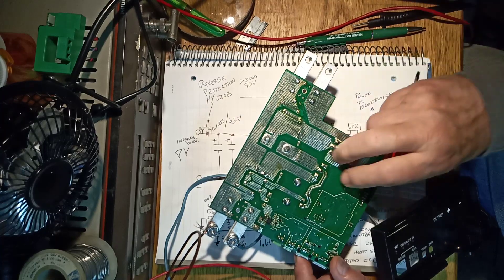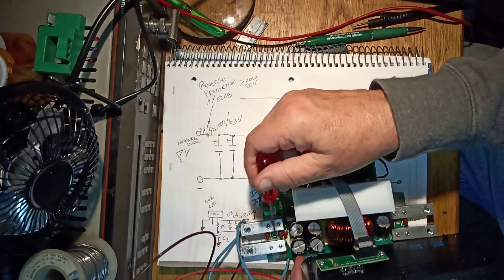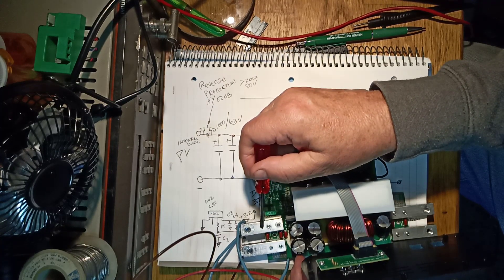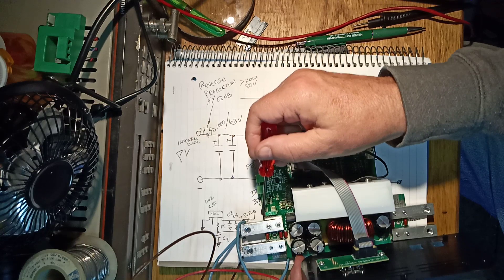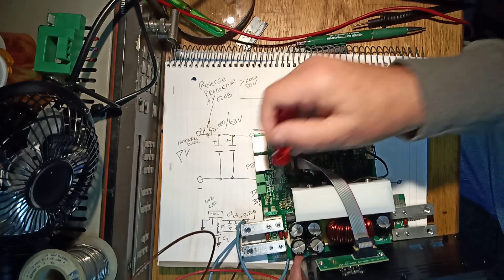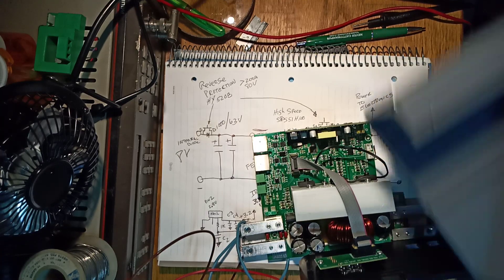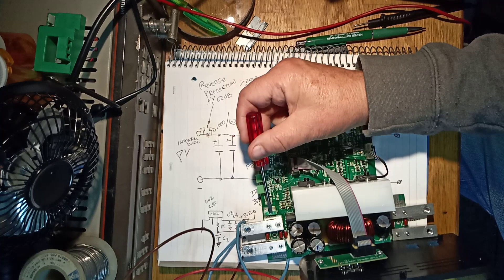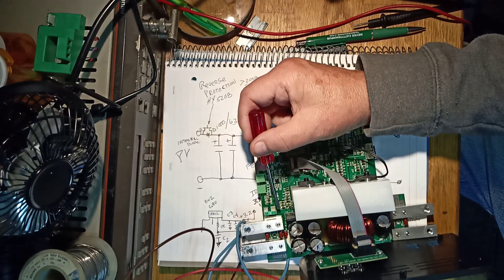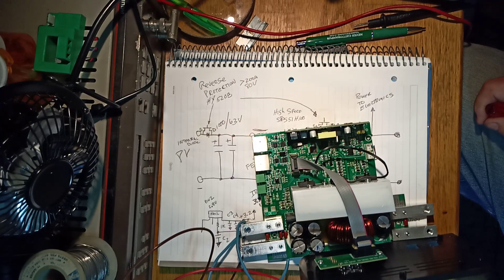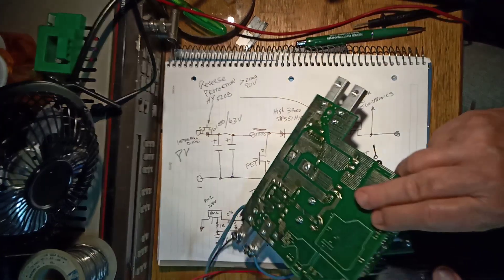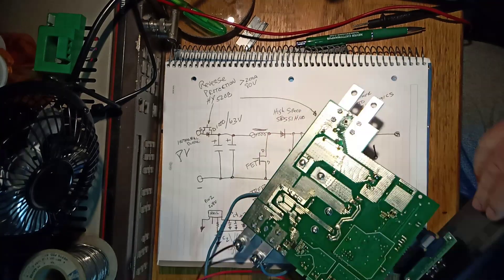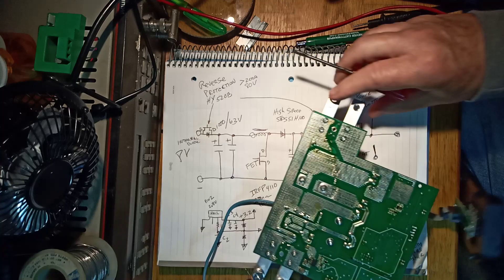So why did you have this problem? Right here, this is supposed to be 10 amps going to the battery. So what did they do? They put in a 30 amp fuse. If they had put in a 15 amp, this thing probably would have survived, that Hall effect sensor. And the fuse would have blown. But no, that's not what they did.